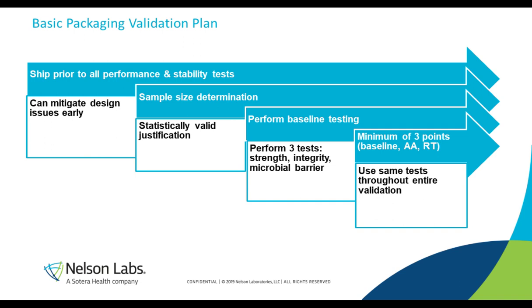Another key point is the sample size determination. It needs to be statistically valid justification. The historical act of picking a sample size of 11 or 30 or 33 because that's what everybody does is no longer an accepted practice, and the decisions behind why you select your sample size need to be documented as part of those validation plans. Now that you've got your prototype set up and you've established your statistically valid sample size, you're ready to start testing.